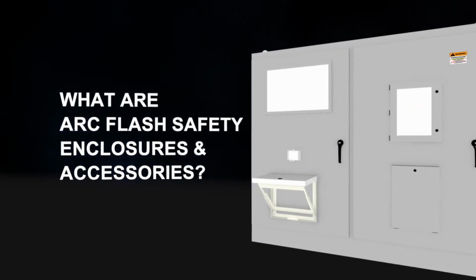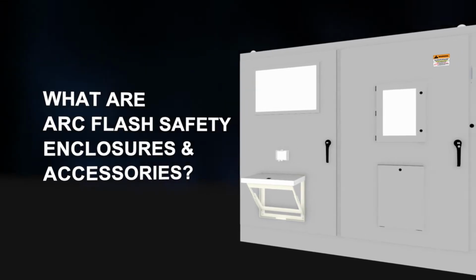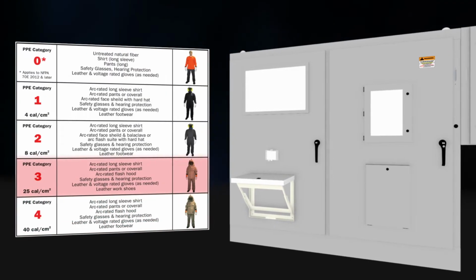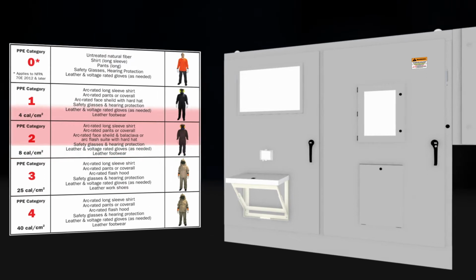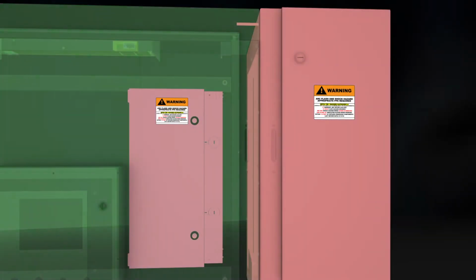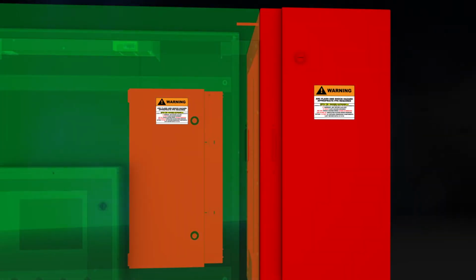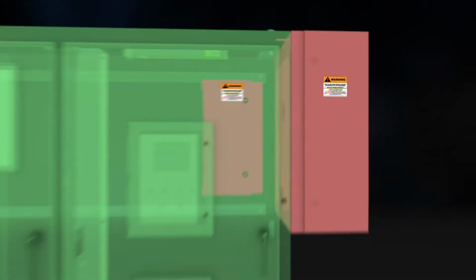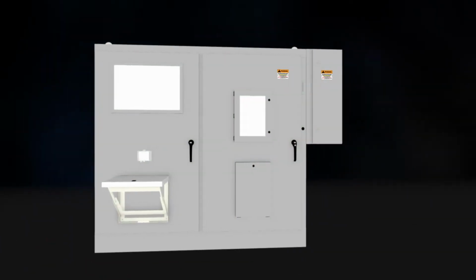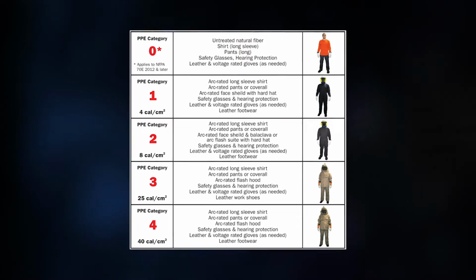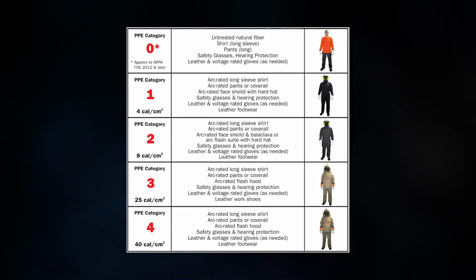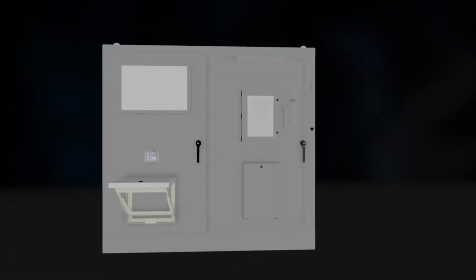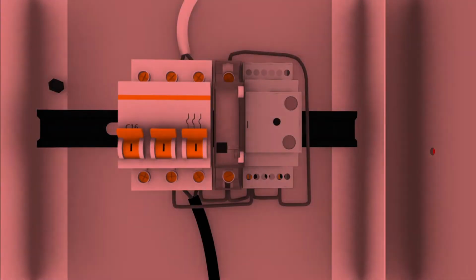So what are arc flash safety enclosures and accessories? Arc flash safety enclosures can assist in lowering the PPE required when accessing an enclosure or part of an enclosure. This can be done by creating an additional barrier between the worker and a higher risk area. This is done by lowering the risk at commonly accessed service areas that would otherwise require a much higher level of personal protection equipment.